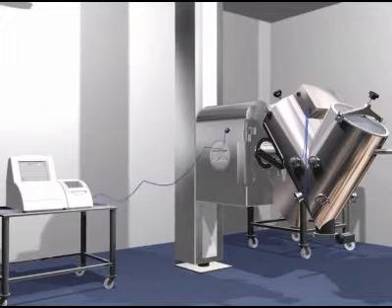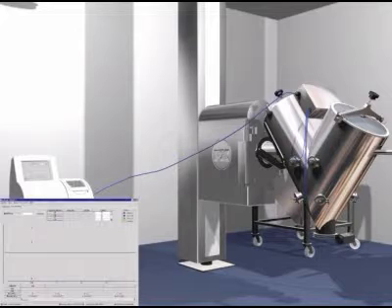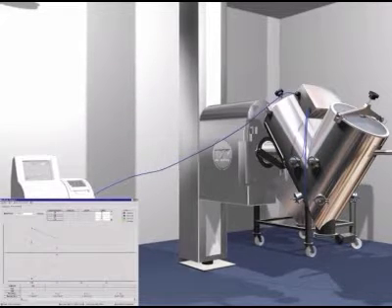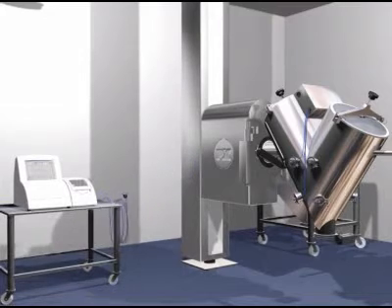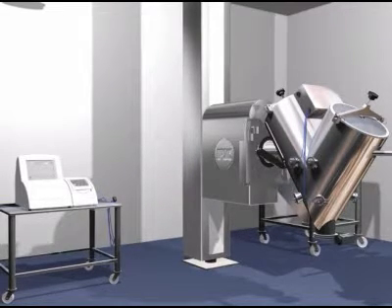Until a wireless communication package is complete, the blender is stopped at intervals to conduct the measurement. The measurements of effusivity are graphically displayed on the software. The software plots the effusivity versus blend time. Each set of results will become progressively closer as uniformity is reached.